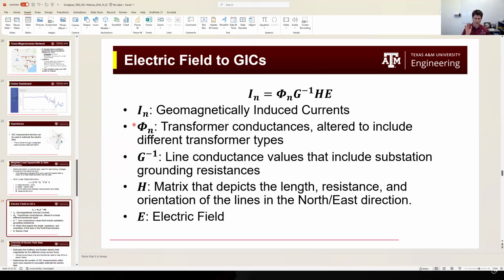if all the IBRs do is inject real power onto the grid, during a GMD the transformers consume more VARs, and so the system needs additional VARs being supplied, and the IBRs wouldn't be able to do that. Now, grid following, if I said grid forming, I meant grid following. Sorry. But if we have grid forming inverters with, say, a QV droop, that would adjust the reactive power output of the IBR-based generation to increase the VAR injection in order to maintain voltage, then that can help mitigate a lot of that.